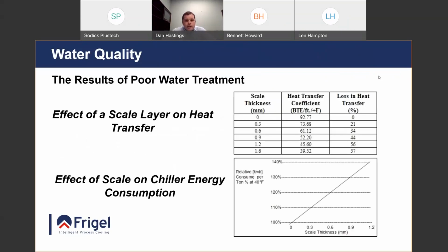I thought this was an interesting diagram that I want to share with everybody, which is kind of the impact of what a layer of scale on the inside of a tool or a heat exchanger or your feed throats actually does. It doesn't take much scale to have an insulating effect and really rob your cooling system of good heat transfer. As you can see right here, if you have just a millimeter layer of scale on the inside of your molds, and inside of heat exchangers, you're really taking away 50% of the heat transfer automatically.